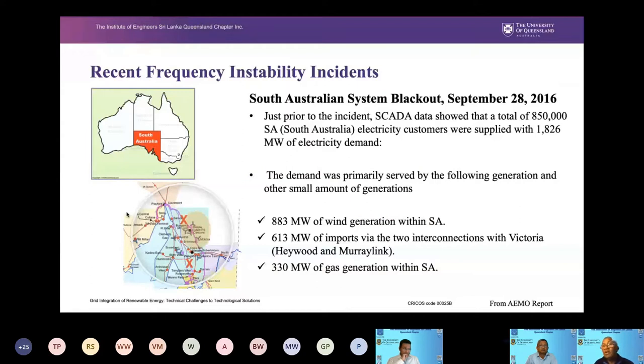So this is where I wanted to bring two incidents which happened recently, to highlight the problem and some commonality. One was in South Australia, where we had a large amount of wind penetration. And the other one is the East England blackout that happened just last year. When we look at the South Australian blackout that happened on the 28th of September 2016, just prior to that incident, the SCADA, the data acquisition system, showed 850,000 customers were supplied with closer to 1,800 megawatts of electricity, South Australia alone.